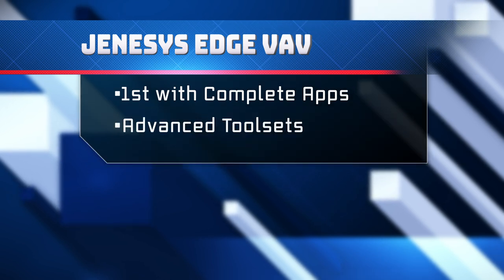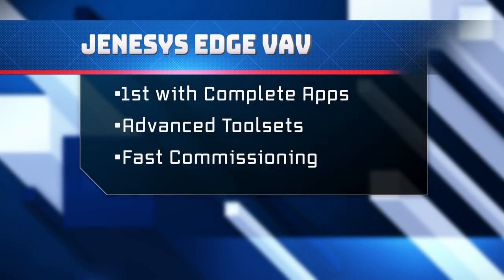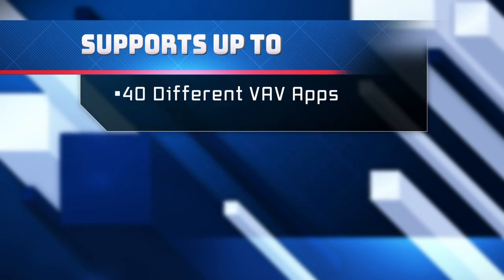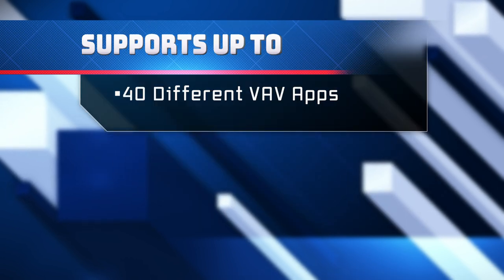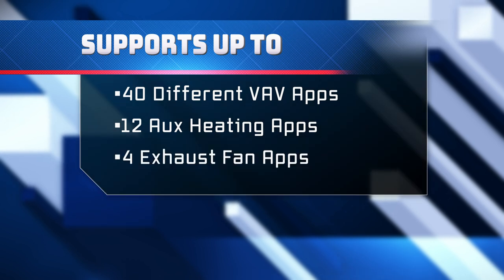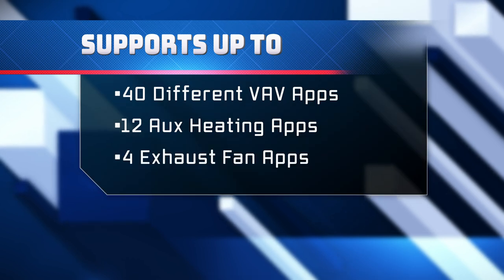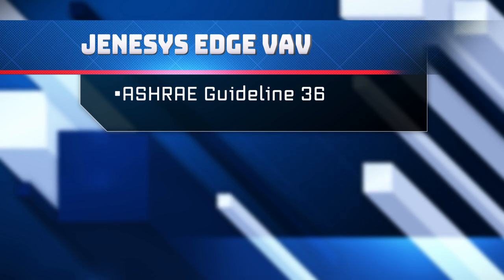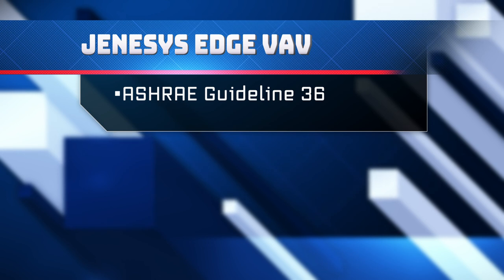The Edge VAV includes tool sets for fast, convenient commissioning and balancing. The Edge VAV supports up to 40 different VAV applications, 12 different auxiliary heating applications, and 4 different exhaust fan applications. The Edge VAV applications are based on established ASHRAE Guideline 36 control sequences of operation.